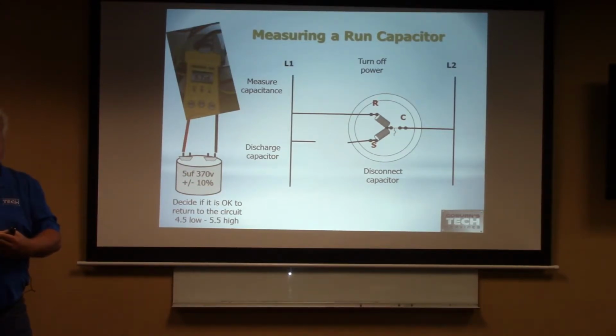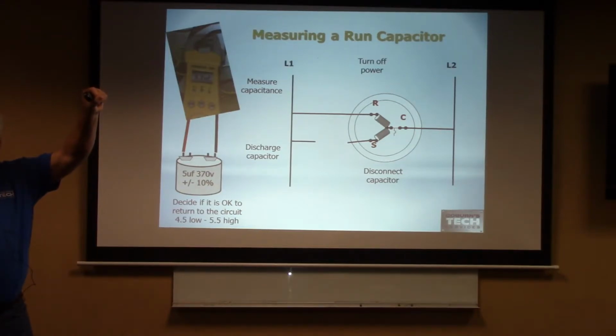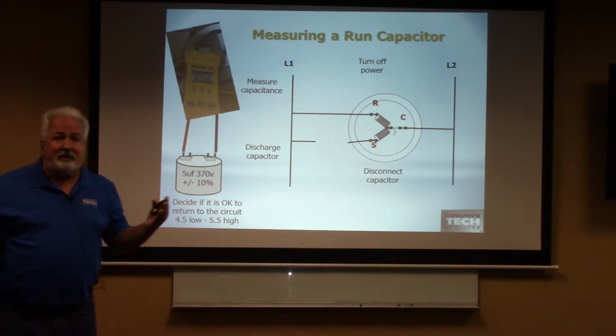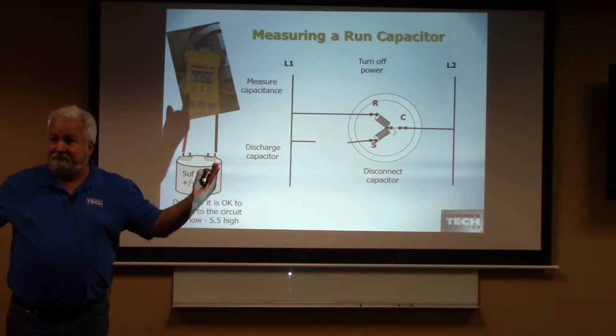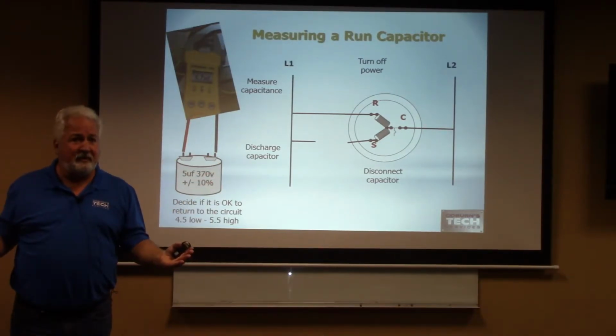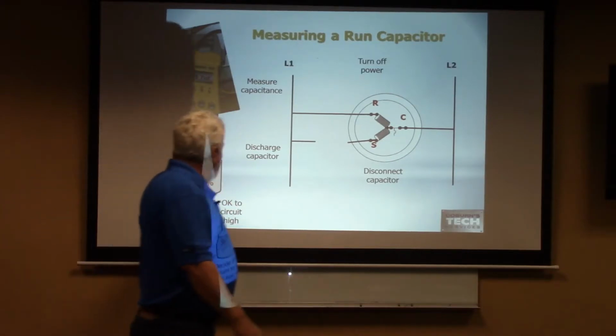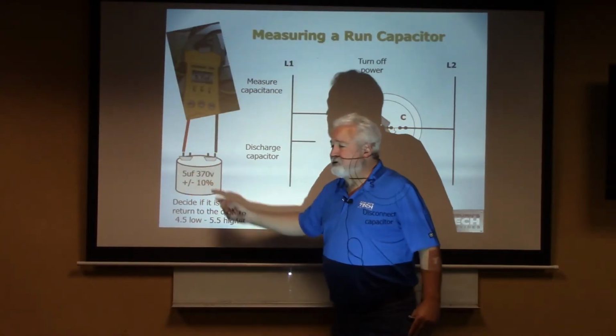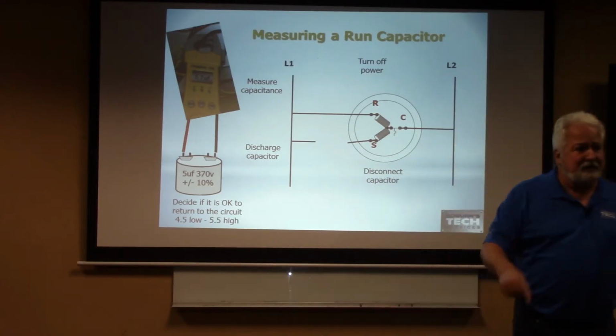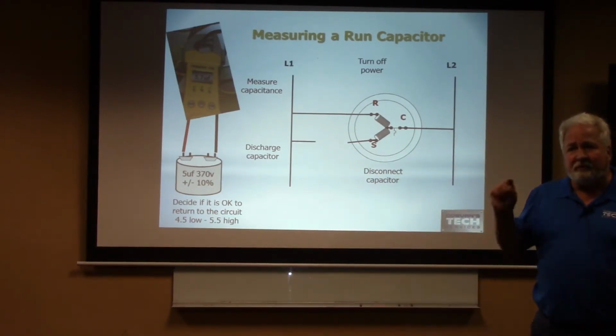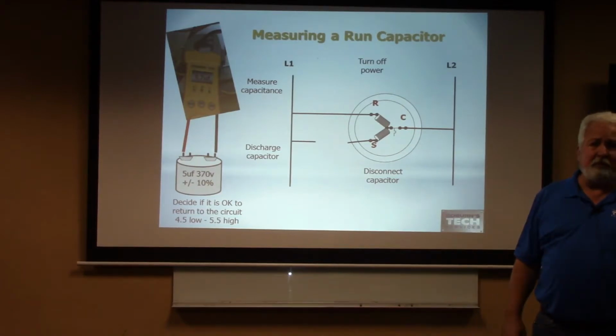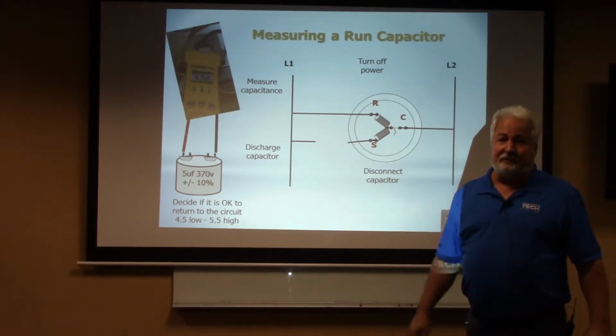Does that make sense to you? All you did is take that bottom pedal and you either moved it here or you moved it here. You didn't get it right where it needs to be. And now it's just going to operate. What's that going to do to the system over the big picture? It's going to take it out, yes? Is that making sense? But you need to understand what it says. It said it was 5 microfarads plus or minus 10%. If I just plug that into my calculator, 5 times 10%, it's going to tell me that that's 0.5 is my tolerance. You go above it. What's the next technician behind you going to say if he measured it?